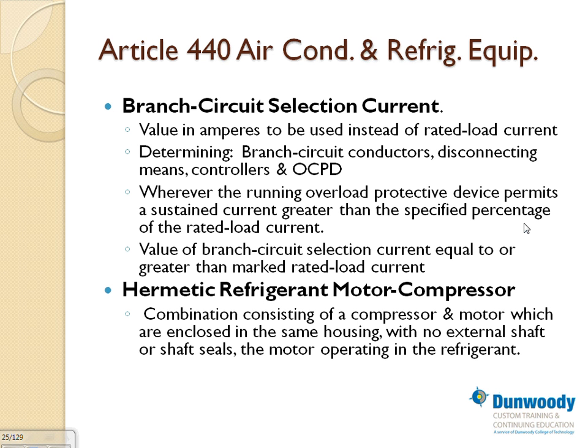That's the conductor size. Now the second thing is the fuse size or the circuit breaker. Right on the nameplate of this HVAC equipment, they will tell you, I need a 100 amp fuse or 100 amp circuit breaker or both. So if the nameplate says 100 amp fuse, you can't put in a circuit breaker unless it says fuse or circuit breaker. Then you can put in a fuse or circuit breaker. So you don't do any calculation really. They size it for you.